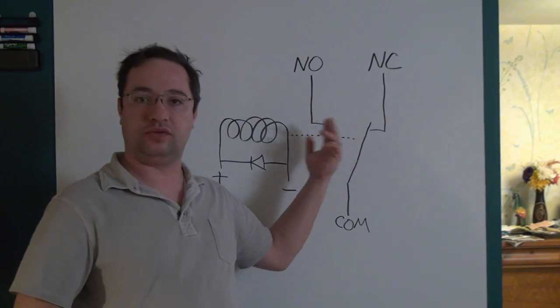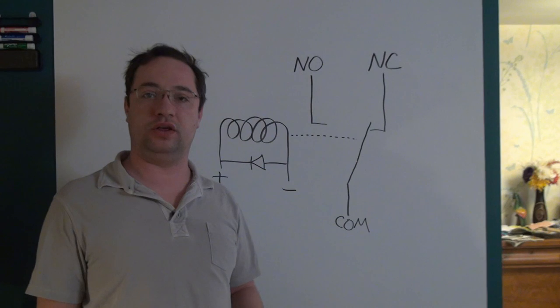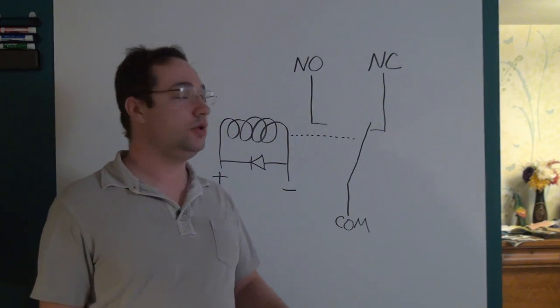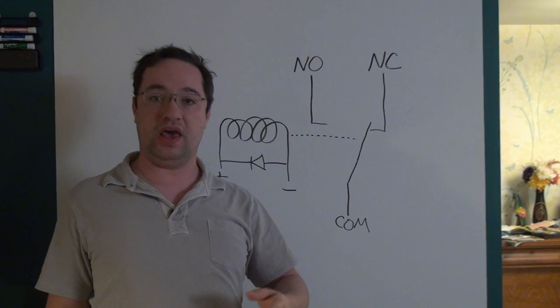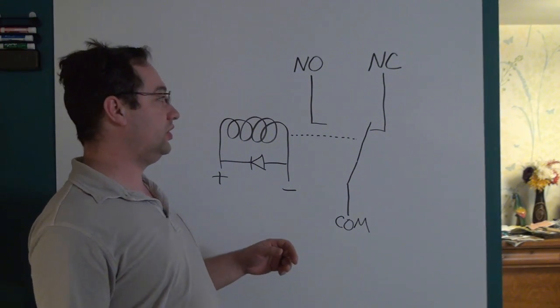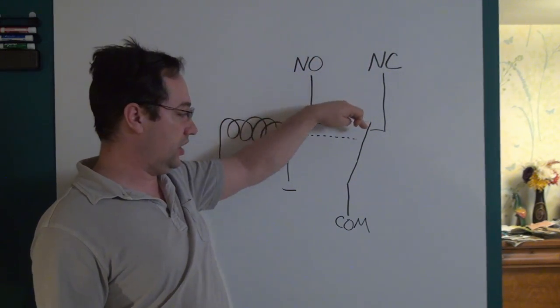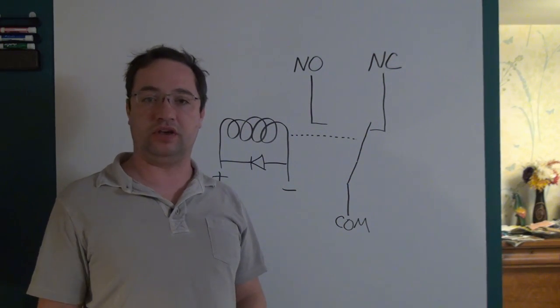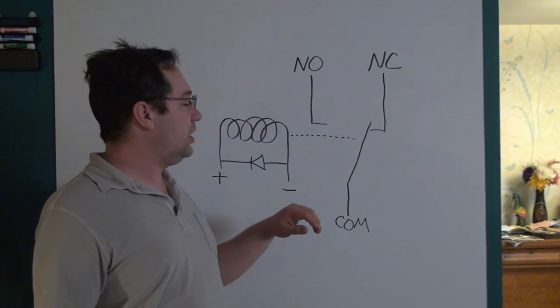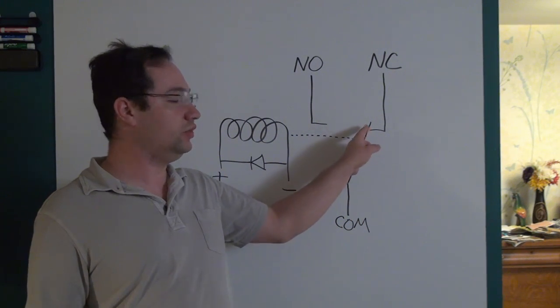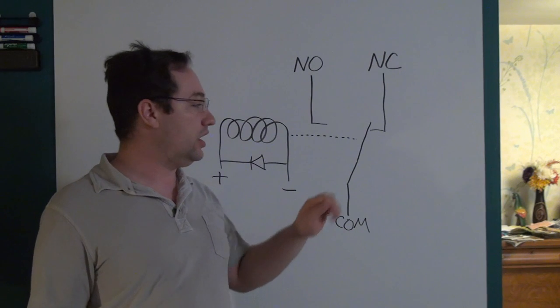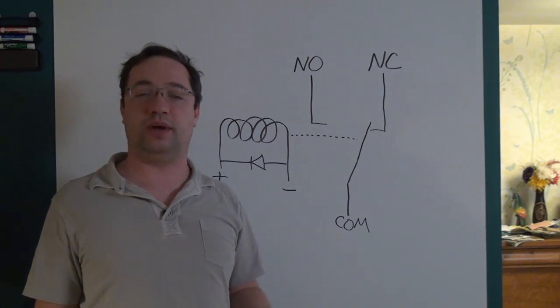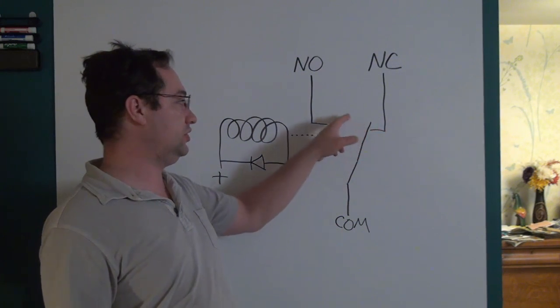Because of this arcing effect whenever the relay contact switches, the current rating for AC is usually substantially larger than for DC. The relay may also have a max current rating — reflecting what the wiring and movable parts can handle — versus a breaking current, which is generally lower, because breaking a large current creates arcing, and arcing can damage the contacts.